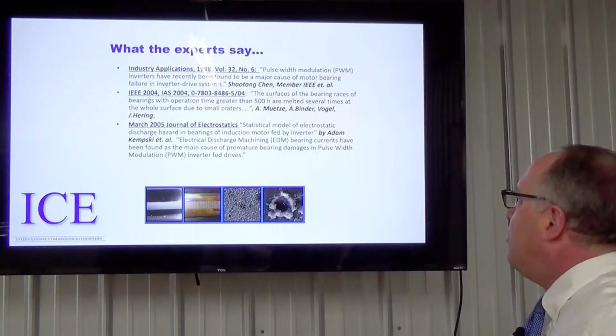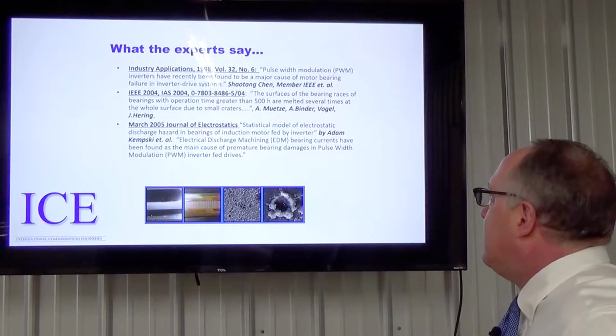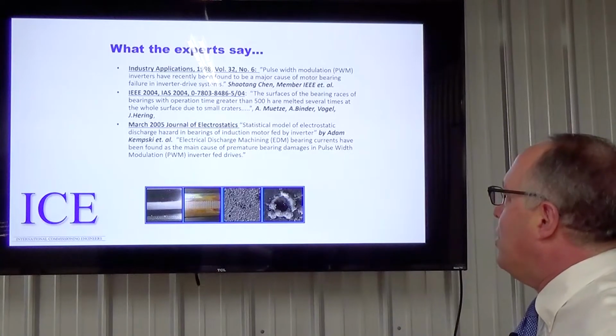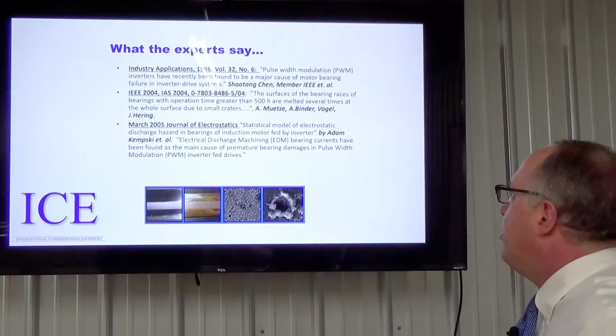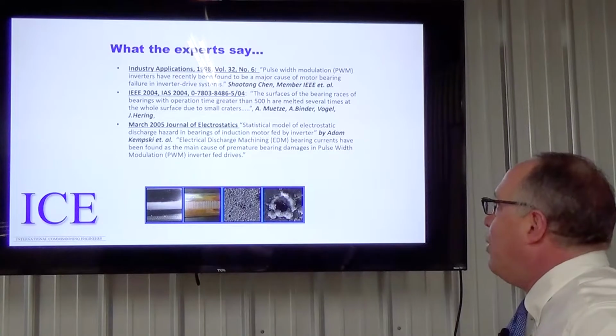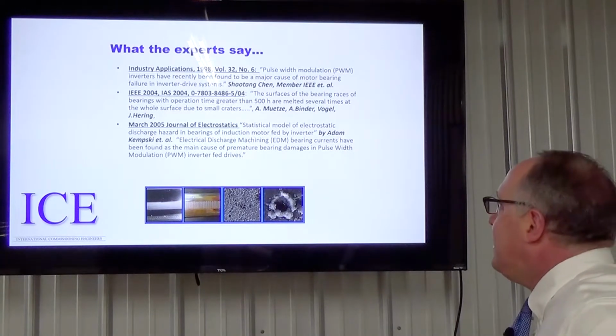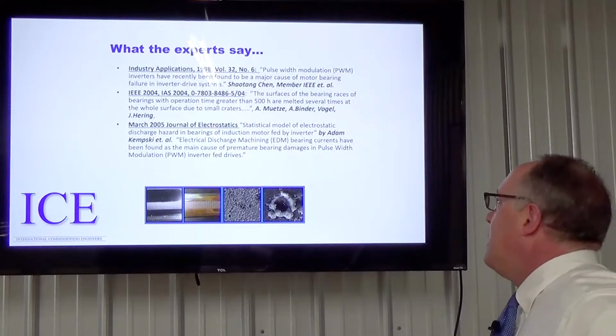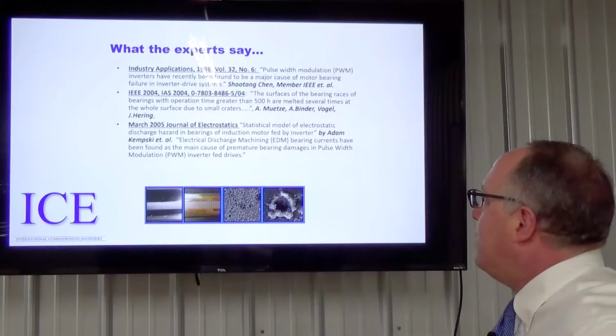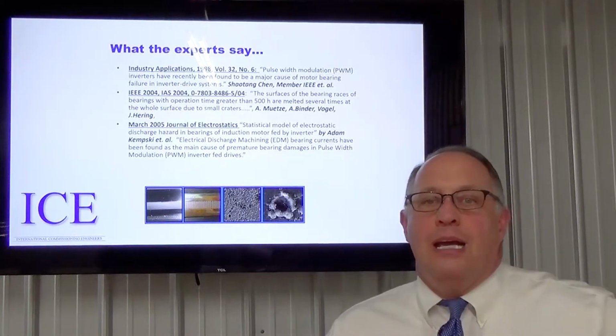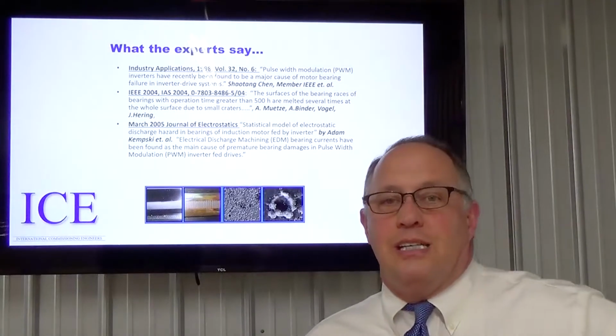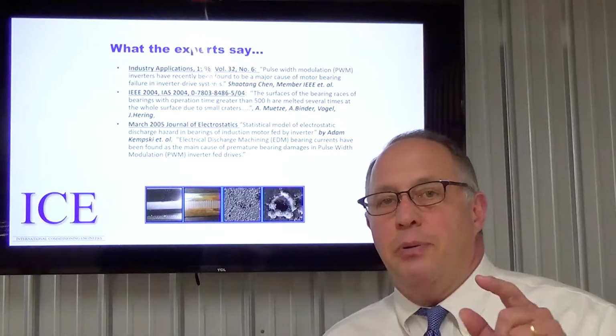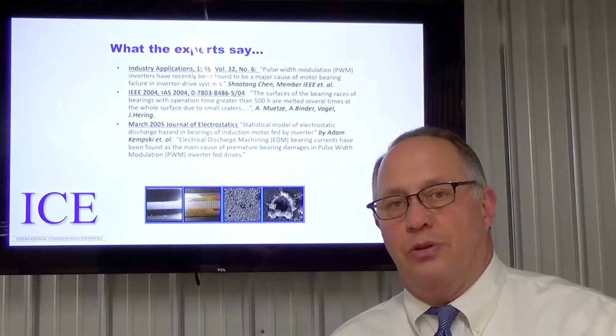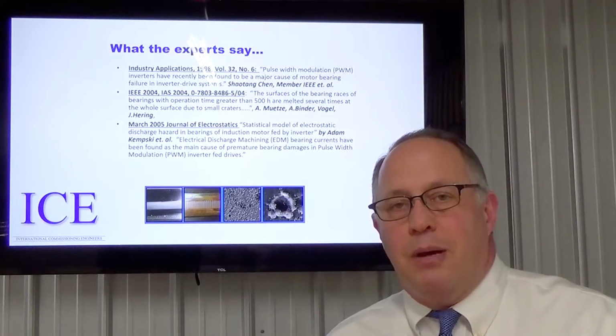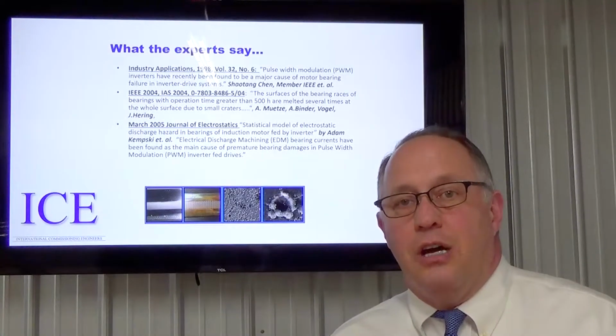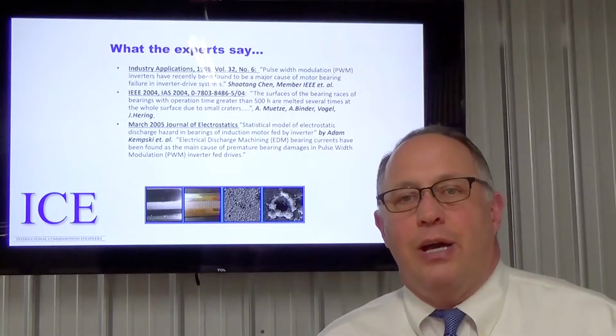And finally, in the Journal of Electrostatics, the statistical model of electrostatic discharge and bearing of induction motors that are fed by an inverter causes EDM, electrical discharge machining, bearing currents that have been found to be the main cause of premature failure. In fact, in other industries, it's said that up to 90% of all motor failures that are driven by VFD are the result of this type of bearing failure.